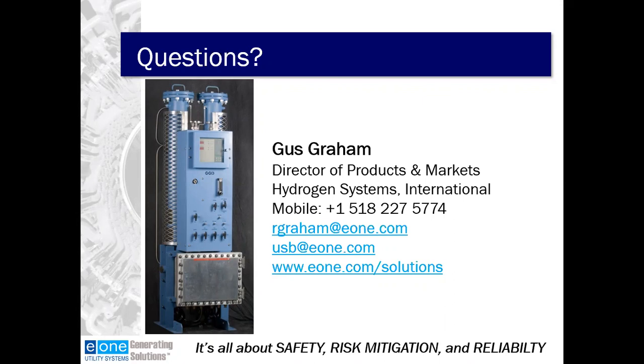Okay, and there was a follow-up to that last question. There were some clarification issues. So it's purging hydrogen out of the dryer, not regen. Oh, I'm sorry, purging hydrogen. Yep, no, that's good. So purging is 15, 20 minutes. We want to look for a minimum of two volume changes of gas flowing through the towers at that point in time. So depending on the regulator setup, the pressure you're delivering the gas at, you're looking at 30 minutes in that range to an hour max.